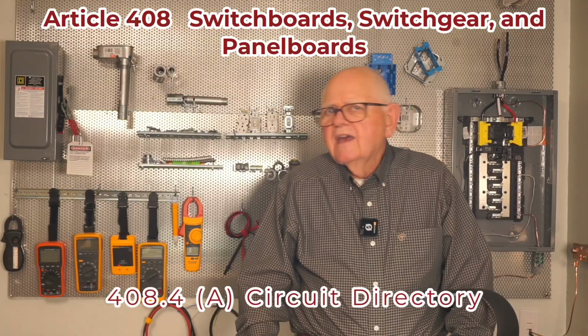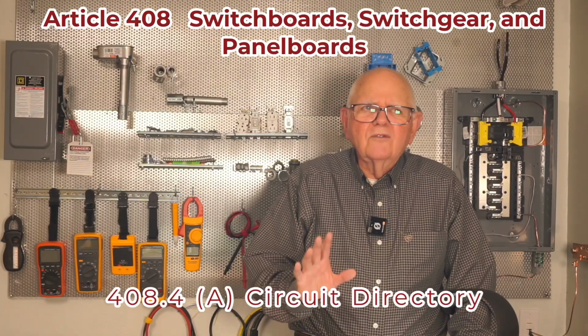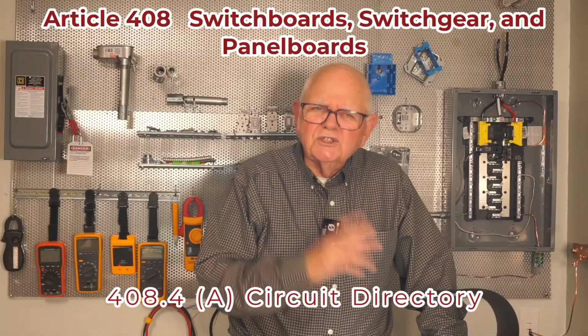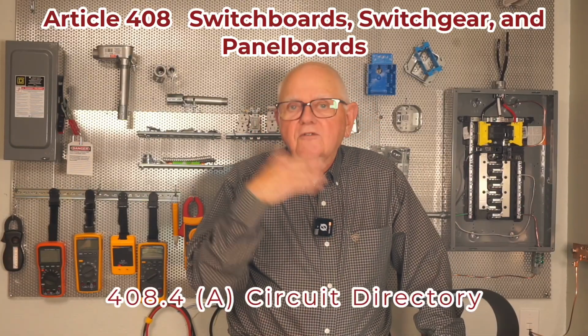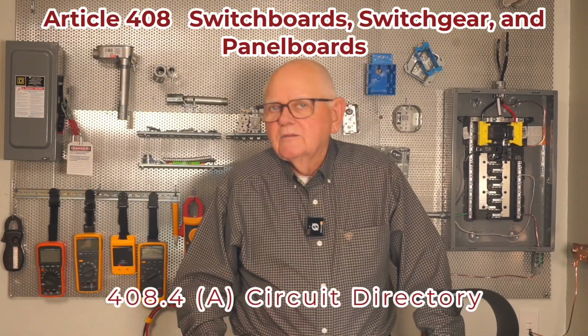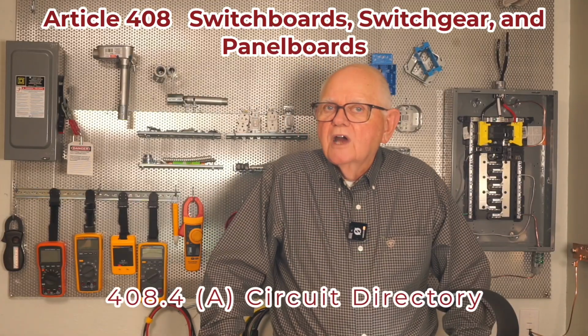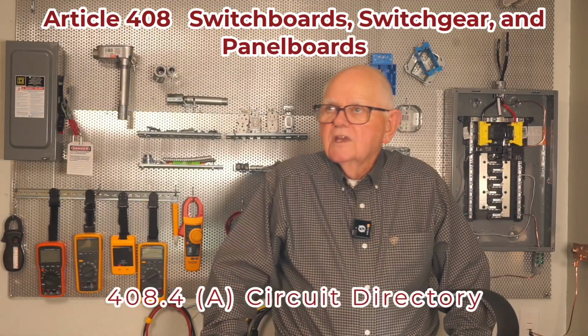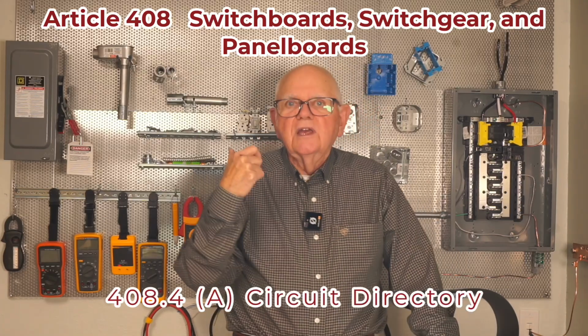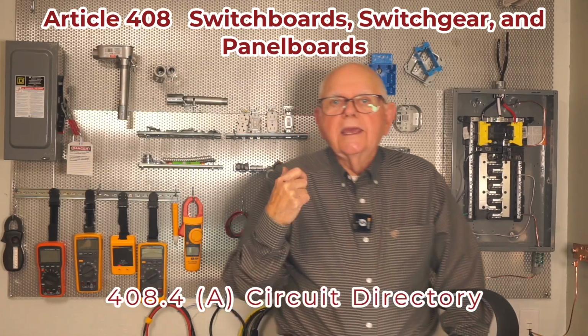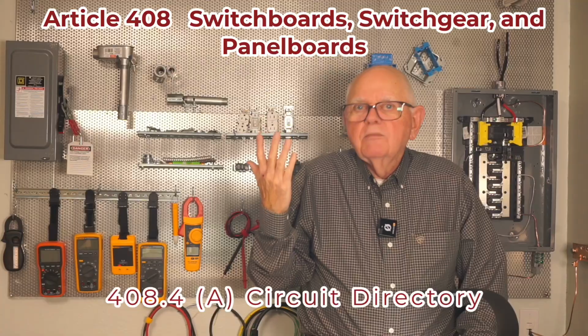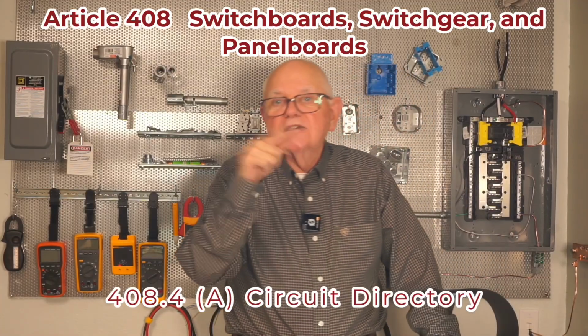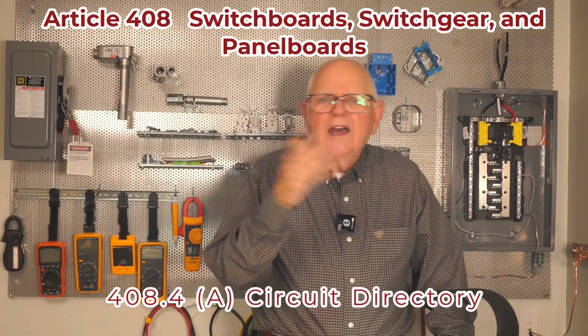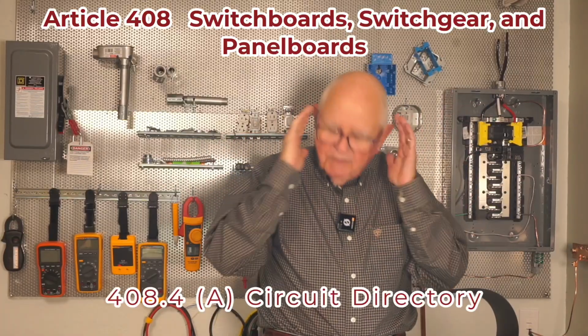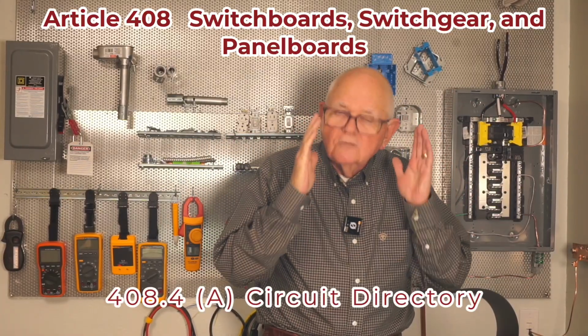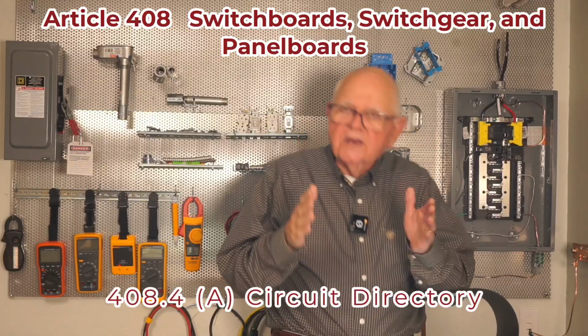Also, it tells me that if I use any type of abbreviations or symbols as part of my circuit directory, I have to identify that on my circuit directory so people know what we're talking about. And we do that a lot, actually. So let's say that Mary's office is actually room 201 in building 2. So maybe we designate that as 2-201. Whatever we're doing, we need to make it clear to people so that when they look at that circuit directory, they know what breaker to go shut off.